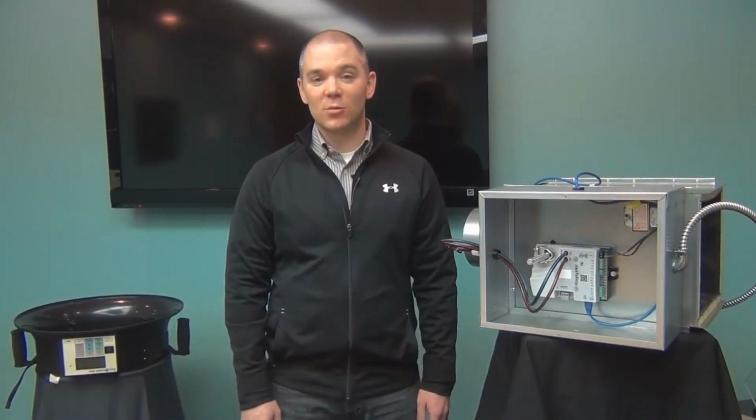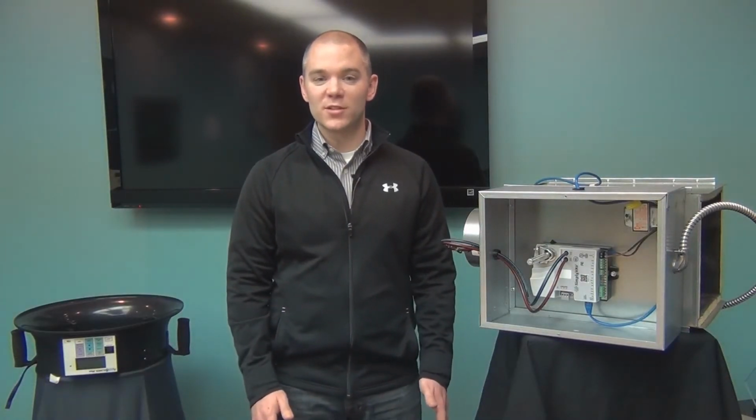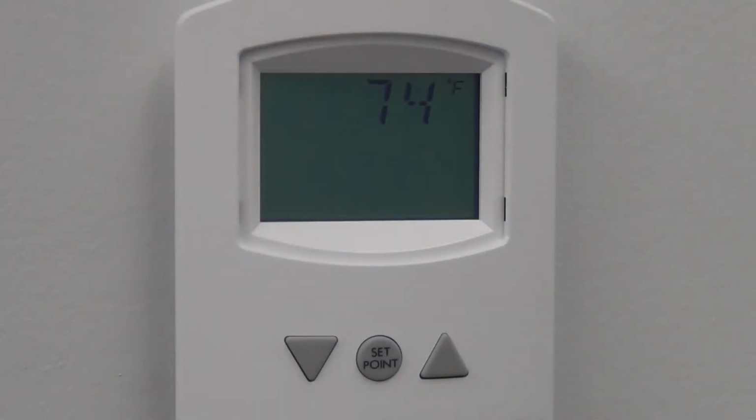In this video, we're going to balance a SimplyVAV controller installed in a single duct box. The only tools required are the digital room sensor and an airflow hood. Once a controller is configured with box settings and flow limits, the balancing routine may be performed.